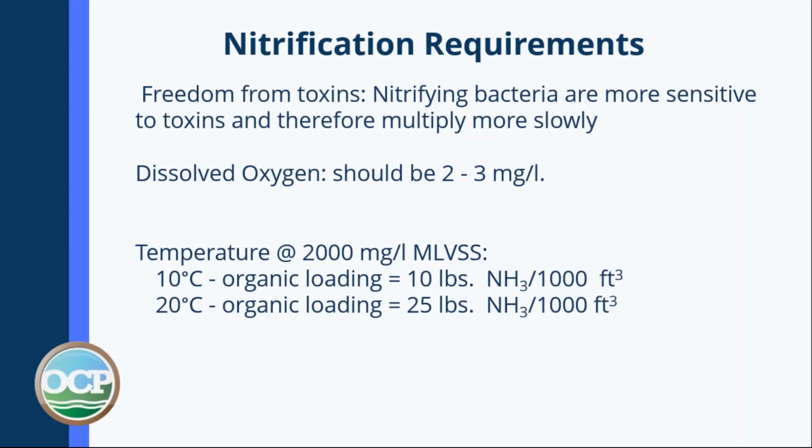Your temperature, as we always see: at 2,000 milligrams per liter of mLVSS at 10 degrees C, you can only treat about 10 pounds of ammonia per 1,000 cubic feet. At 20 degrees C, warmer temperature, that goes up to 25 pounds of ammonia per 1,000 cubic feet.